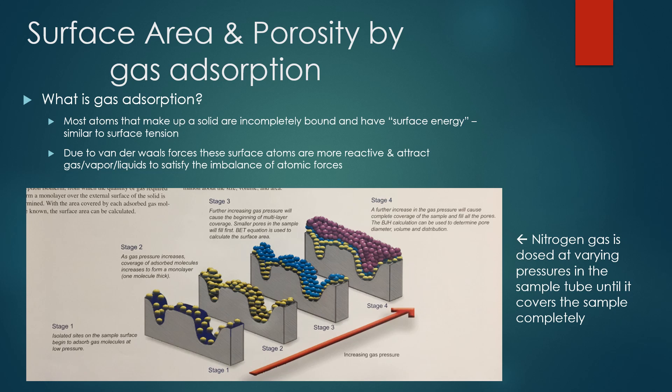The instrument doses nitrogen gas at varying pressures into the sample tube, and the surface of the material attracts that nitrogen gas and eventually covers the surface in a monolayer. That's what you're seeing at stage 2 in that picture - that's where we get surface area measurements. As you continue past the monolayer, the molecules fill in the pores on the surface or cavities within the material, and that's where you get porosity measurements.